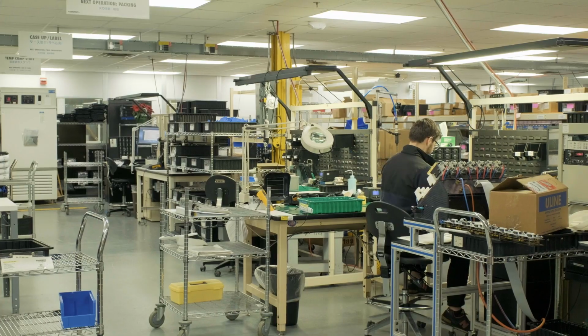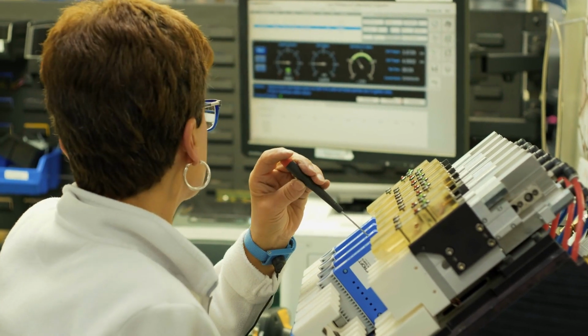What other folks are doing is they're taking a higher pressure sensor and turning the gain up to be able to amplify the output, to be able to get down to 1/10 of an inch or 1/4 of an inch. Regardless of what magic they put into the product, when you amplify an output, there's inaccuracies that are tied to it. The Ashcroft product will provide a true 1/4% terminal point unit, while our competition will have a 1/4% with a 1% zero and 1% span setting. So is it really truly a 1/4%?